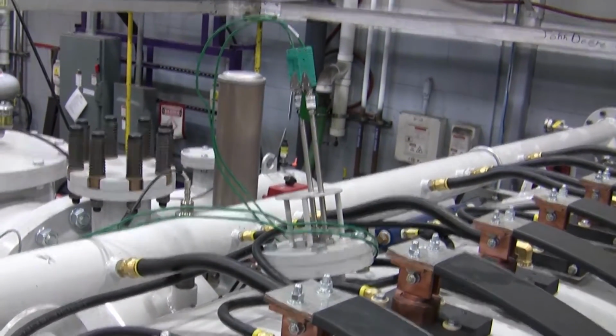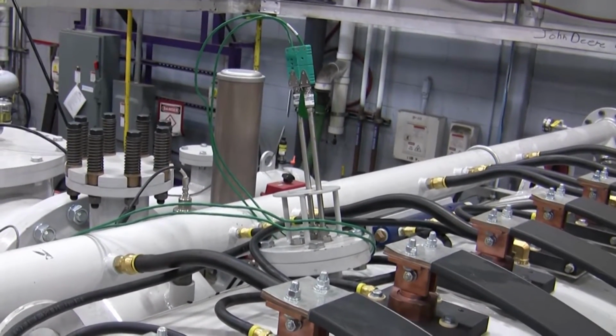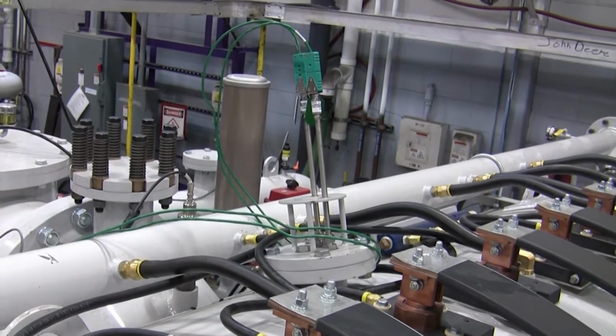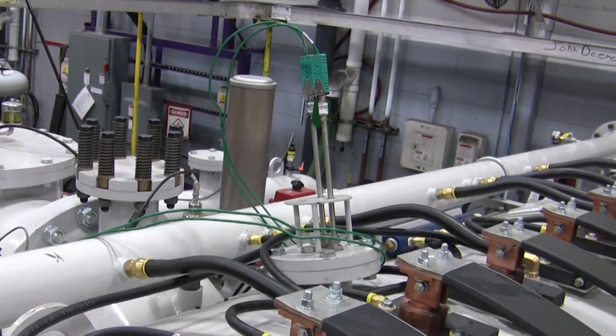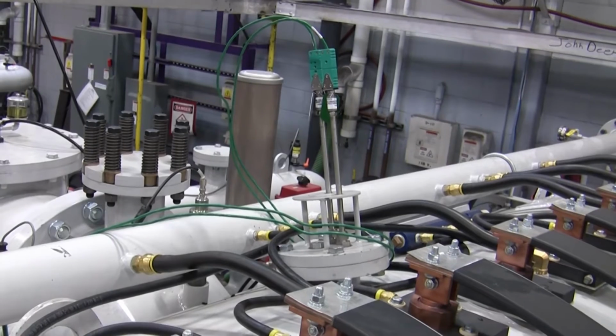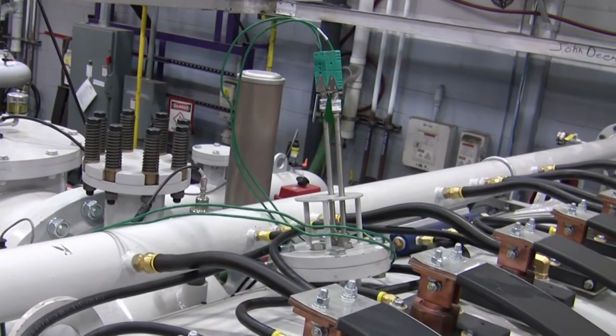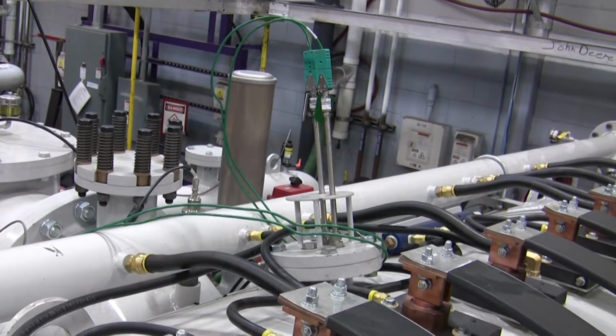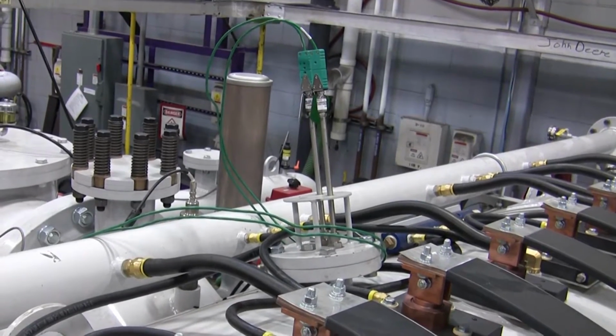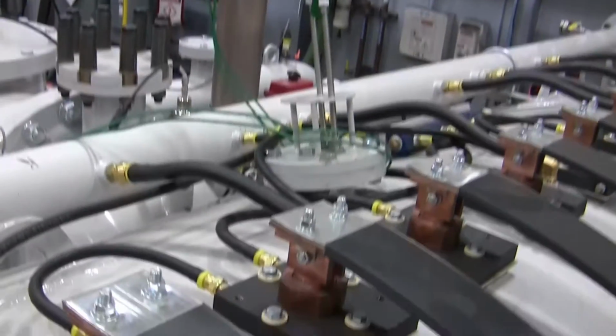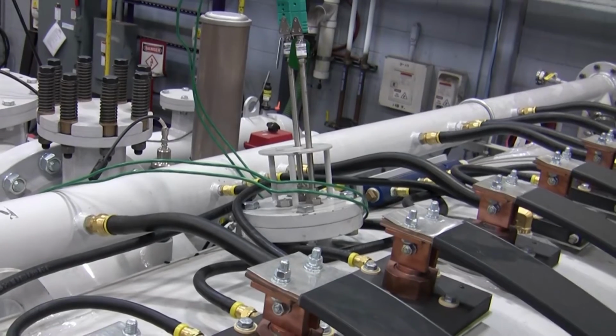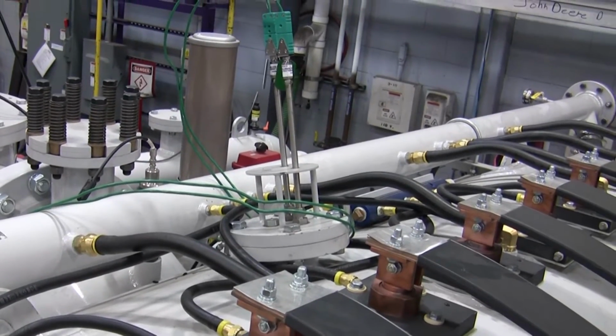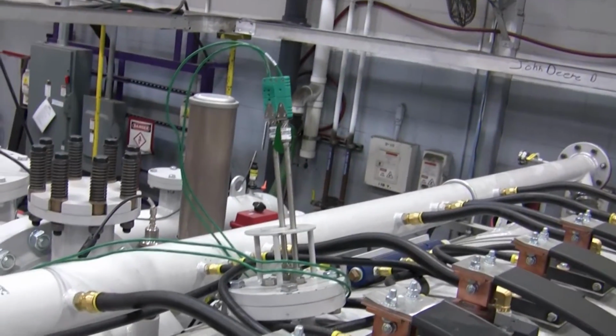I'd like to take a moment and review the control and overtemp TCs. We normally stick with the type S thermocouples, and they're Inconel sheath on the outside and ceramic sheath on the inside, which I'll show you in a minute. And then you can see the gland at the bottom, a compression fitting, which allows for adjustment, which we'll discuss, of the insertion depth of the TC.